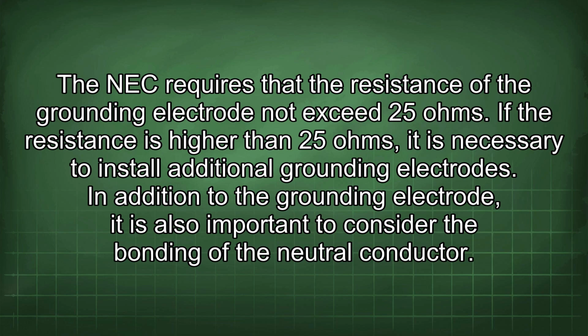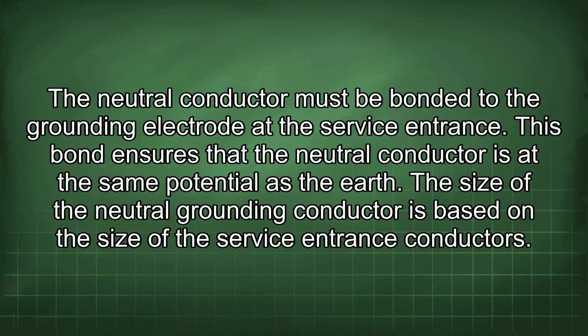In addition to the grounding electrode, it is also important to consider the bonding of the neutral conductor. The neutral conductor must be bonded to the grounding electrode at the service entrance. This bond ensures that the neutral conductor is at the same potential as the earth. The size of the neutral grounding conductor is based on the size of the service entrance conductors.